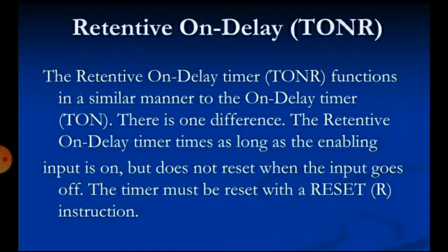Another type of timer is the retentive on delay, that is TONR. The retentive on delay timer functions in a similar manner to the on delay timer. There is one difference. The retentive on delay timer times as long as the enabling input is on but does not reset when the input goes off.